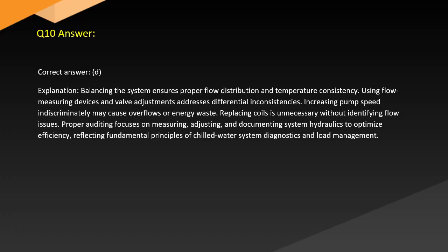Answer. Correct answer: D. Explanation. Balancing the system ensures proper flow distribution and temperature consistency. Using flow measuring devices and valve adjustments addresses differential inconsistencies. Increasing pump speed indiscriminately may cause overflows or energy waste. Replacing coils is unnecessary without identifying flow issues. Proper auditing focuses on measuring, adjusting, and documenting system hydraulics to optimize efficiency, reflecting fundamental principles of chilled water system diagnostics and load management.